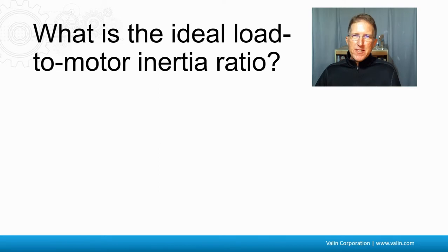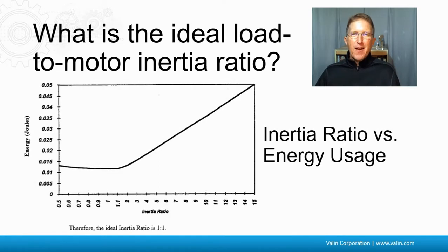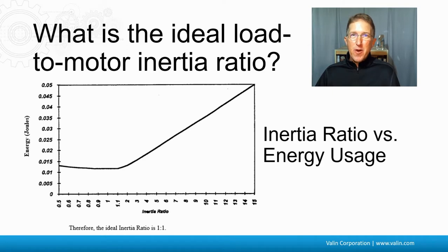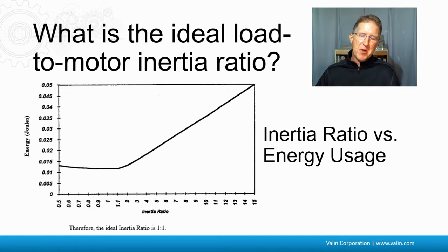That brings us to the question: what is an ideal load-to-motor inertia ratio? Based on a long calculation about energy usage, the ideal ratio is 1 to 1. The problem is that targeting 1 to 1 usually results in a motor that's way too big for most systems. So you're not really going to hit 1 to 1 unless your load is really small.